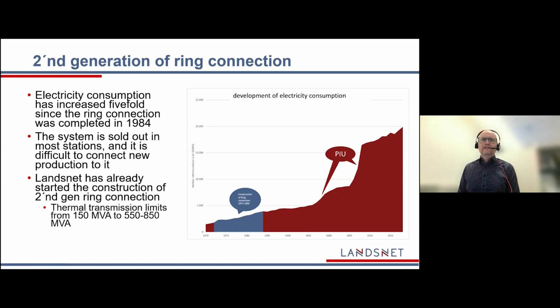By that, we are increasing the thermal transmission limits of the lines from 150 megavolt-ampere to 550 to 850, depending on distances. We are using duplex conductors where needed, so it's 3 to 5 times more transmission capacity than we have today.